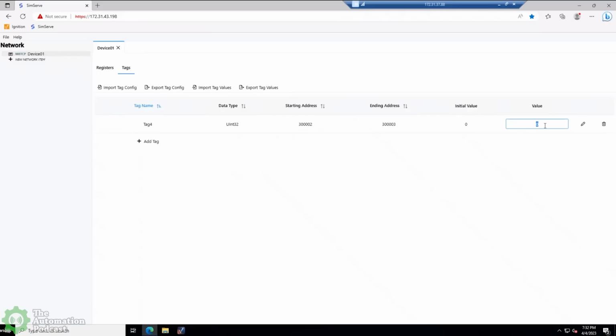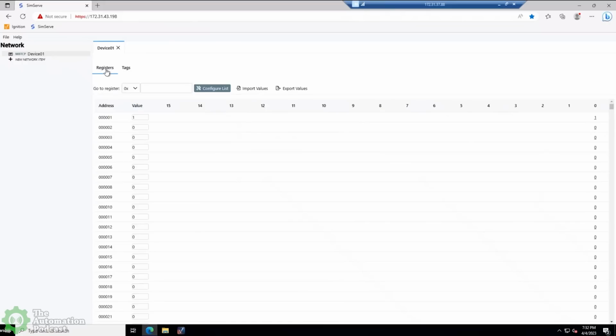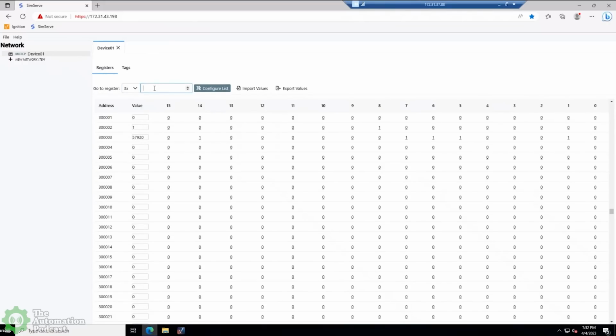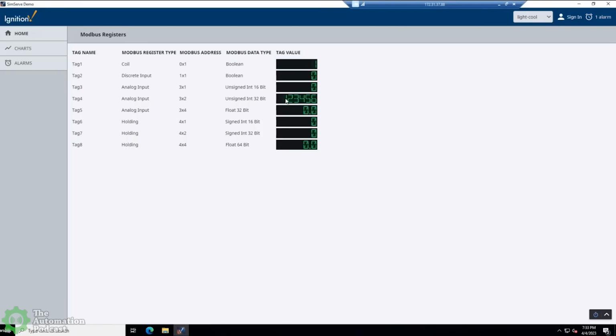I'm going to go ahead and put in a value. Let's do 1, 2, 3, 4, 5, 6. All right, let's flip back over to the registers here. And let's go to that 3x2 register that we just entered in. All right, so you'll see here, 3x2 has a value of 1. 3x3, which is the next register, is the second half of that 32-bit integer, has 57920. Okay, that's because SimServe just calculated the right value for both of these registers. If we jump up to the Ignition HMI, now you see 1, 2, 3, 4, 5, 6. So basically, the same way that Ignition is reading the registers is the same way that SimServe is writing to them. So that's kind of a feature that helps SimServe stand out a little bit in the Modbus simulation world.